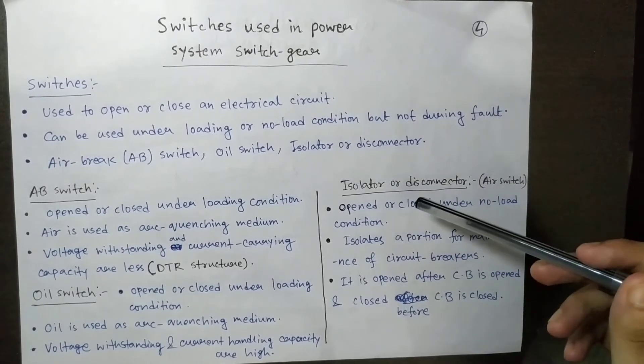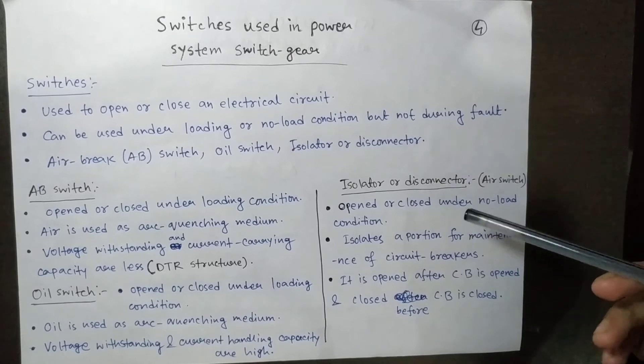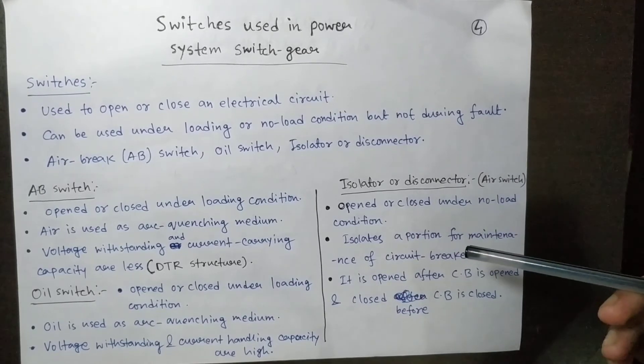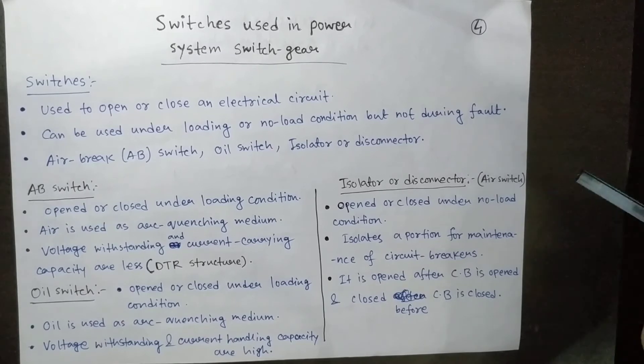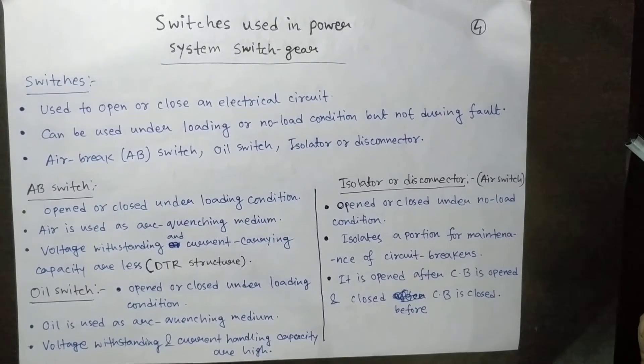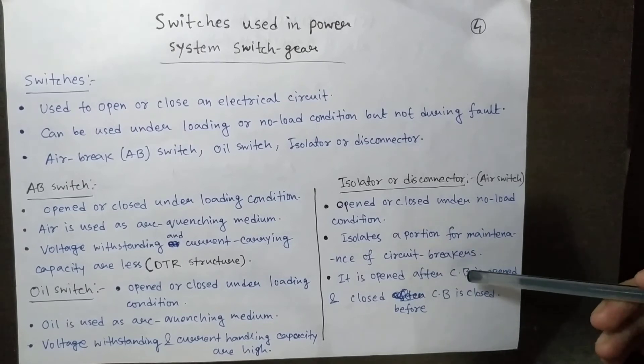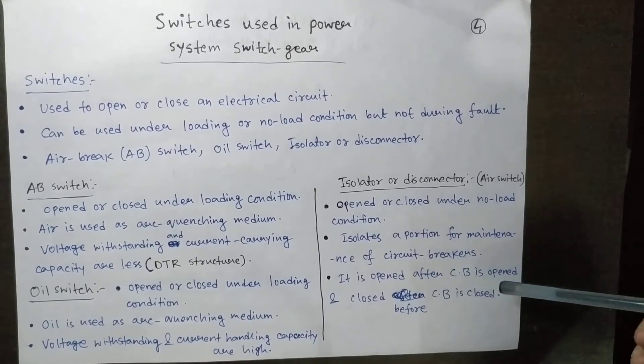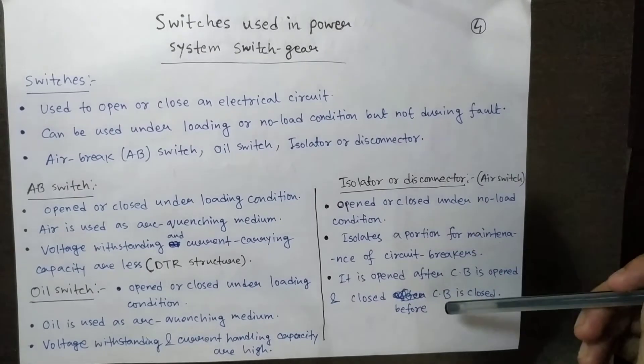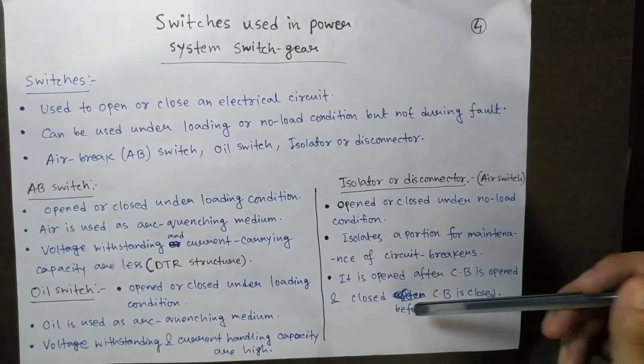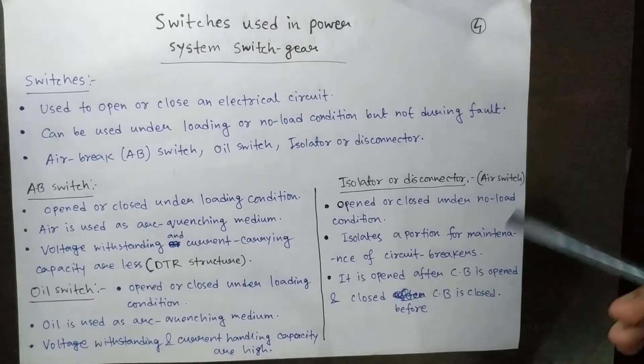Always remember that the isolator does not have arc quenching capacity. If you try to operate it under load, it may burn or get damaged. The AB switch has arc horns that quench the arc, but the isolator does not. The correct procedure is: for maintenance, first open the circuit breaker, then open the isolator. Similarly, before closing, first close the isolator, then close the circuit breaker. This sequence is always followed.